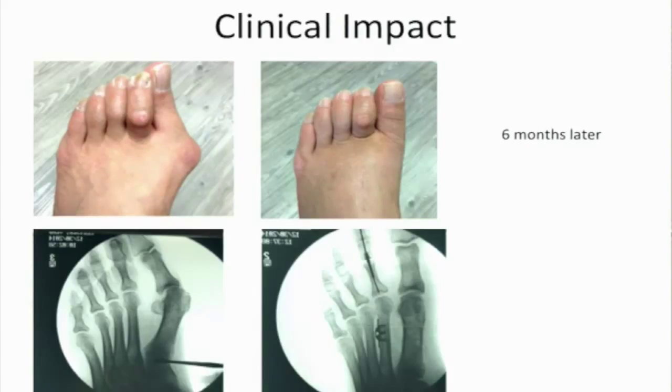I designed that to show you the worst of the case. The worst problem we had was one of the surgeons, and I'm going to blame it on the surgeons. One of the surgeons, we told them they can't bend the plate. The plate didn't fit, so they bent the plate. It's not designed to be bent, and the plate broke into pieces after they closed up and the person was walking around. So that's some of the stuff we have to deal with. And then we had some that failed, just the device slipped or didn't hold or did something.